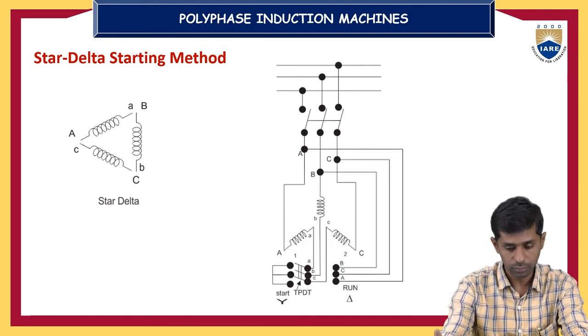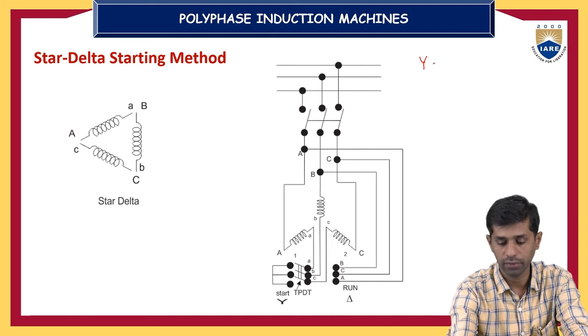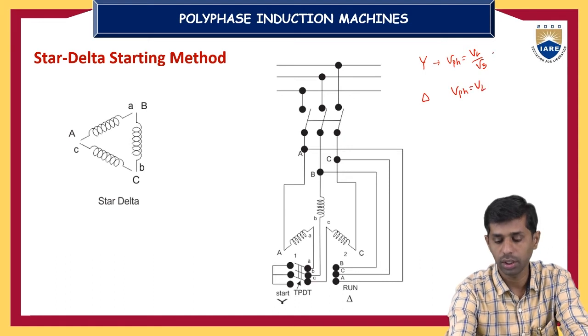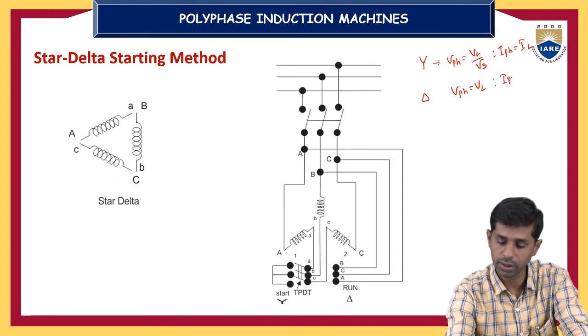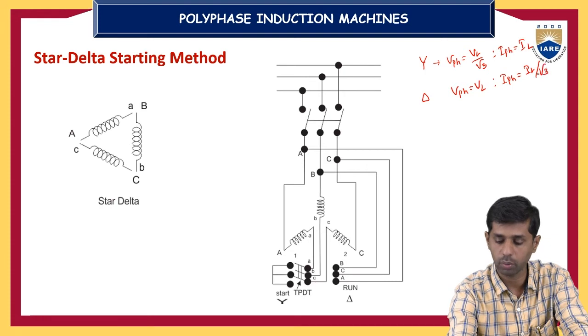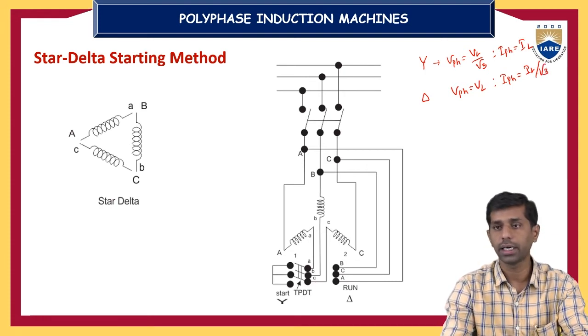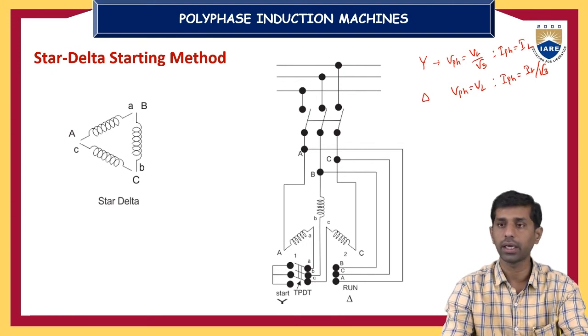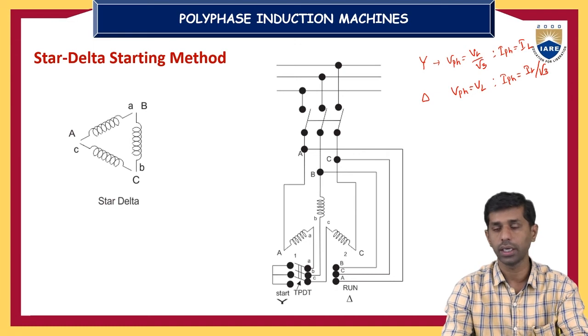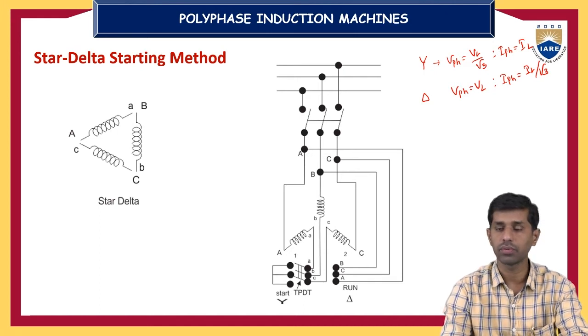And we have a relation: V phase equal to VL by root 3 in the case of the star connected winding. In the case of delta, V phase equal to VL. Similarly, the current relations are I phase equal to IL in a star connected network, and in a delta connected network, I phase equal to IL by root 3. There are a total of 6 terminals from the stator winding, each phase having 2 terminals, a starting terminal and an end terminal. We will have 6 terminals in a terminal box, and depending on requirements, we connect them as a star connected or delta connected stator winding.